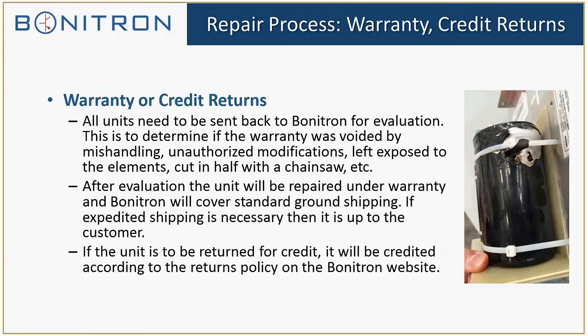So the next question, obviously, is when they need to send it in for warranty or credit. We still need the unit back for evaluation, making sure that there are no problems with how it was wired in, or external damage, like it was dropped off a forklift or something like that, or it was just horribly miswired. In this case, this was a 230 volt capacitor, and it was wired to 480, so it blew a hole in the side. After we evaluate the unit, we'll issue a credit memo to the company, and how we issue the credit is determined by our returns policy, and you can find our returns policy on the Bonitron website under the tab that's marked Contact.